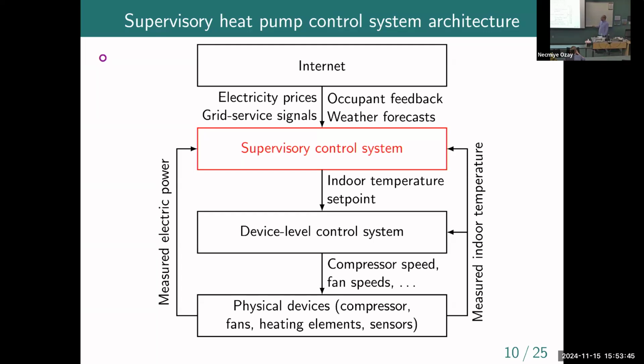The control system also gets measurements. It pulls indoor temperature measurements from the thermostat, which is the same device that sends measurements to the device level control system. We also put in a power sensor, so we have circuit level electric power metering that we can get at about 1 second resolution, and we feed those measurements into the supervisory control system as well. That was about a $150 device, so not super expensive.